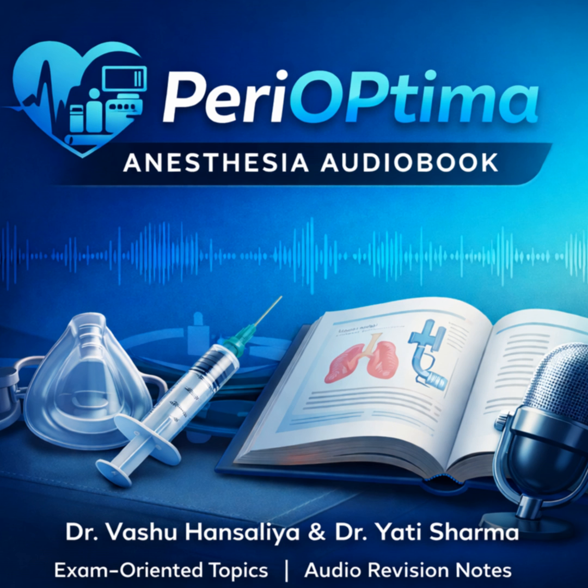That is a terrifying thought. The machine's dial says 100% oxygen, but the patient is actually getting a mix of oxygen and room air because of a tiny silent crack in the glass. That is precisely the danger. And that is why understanding these three zones isn't just for the exam diagram. It's for understanding why the low-pressure leak test is the single most important part of your morning check.